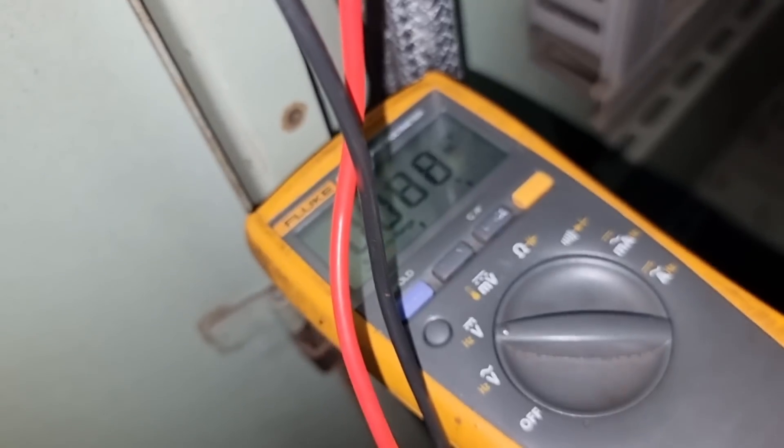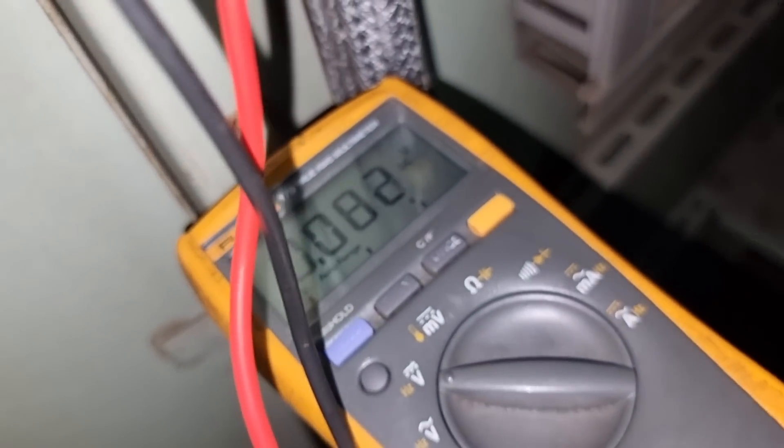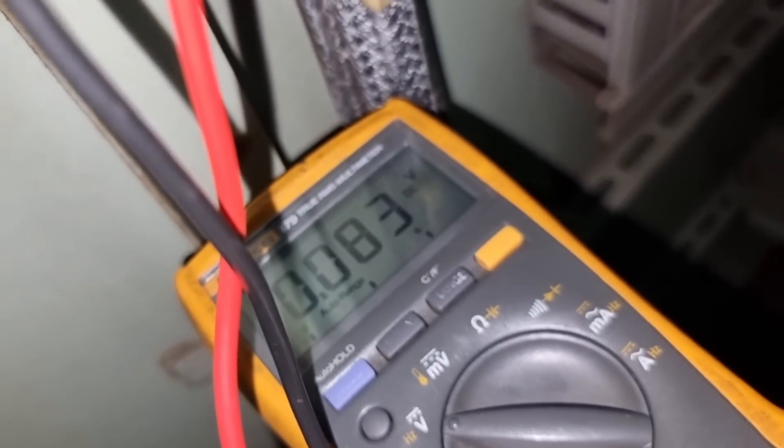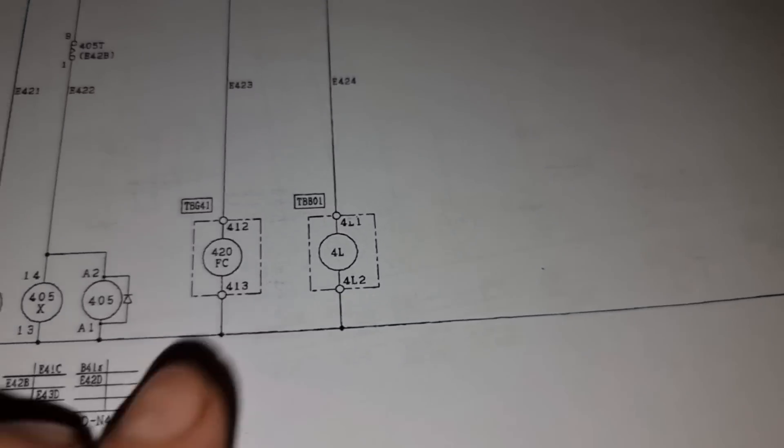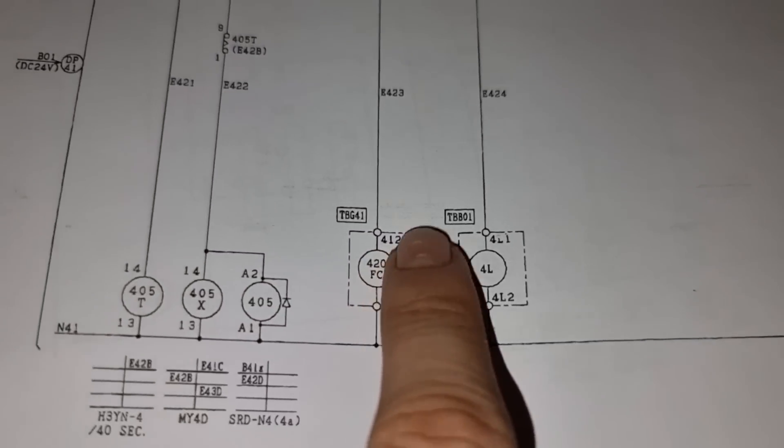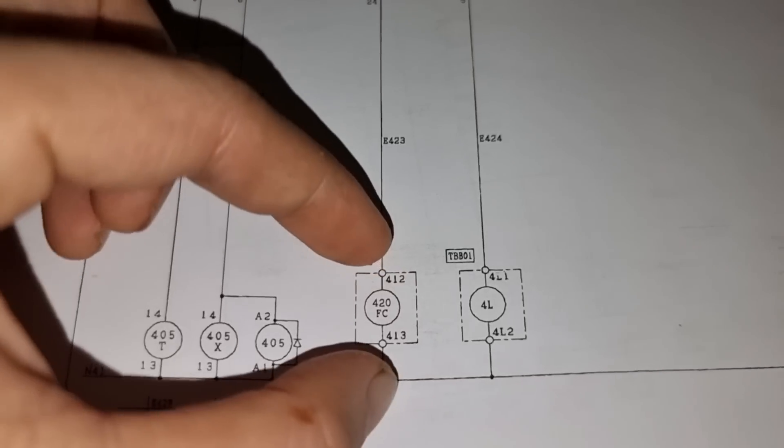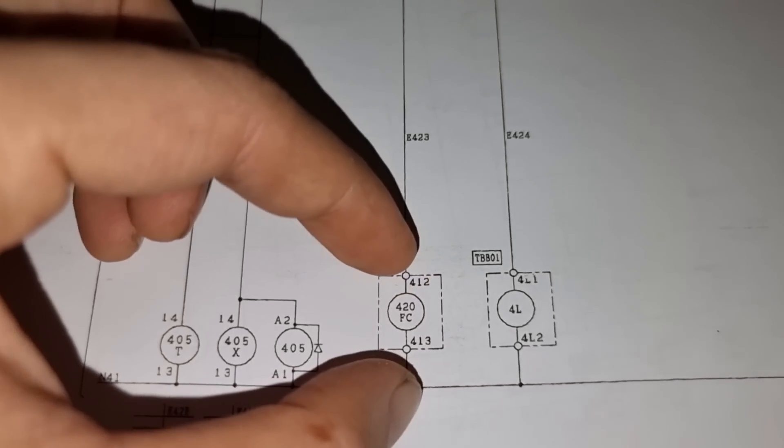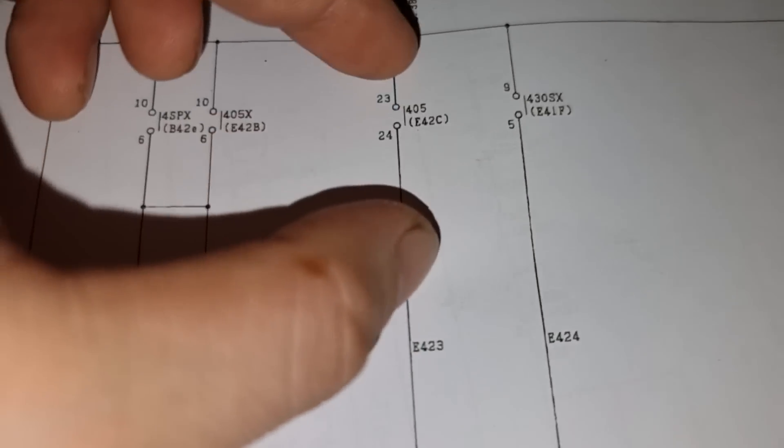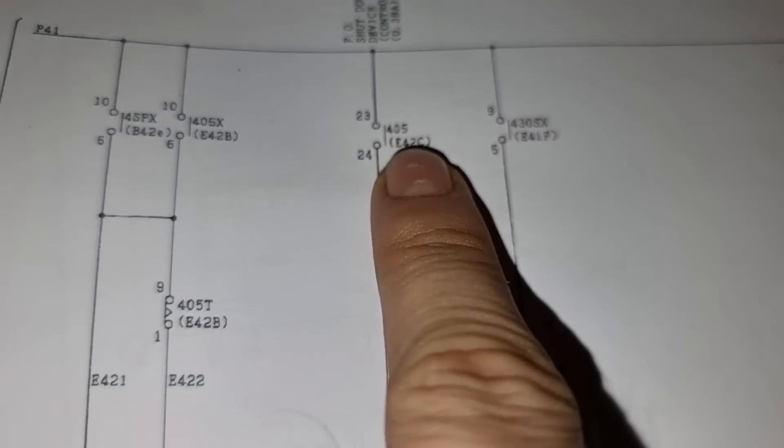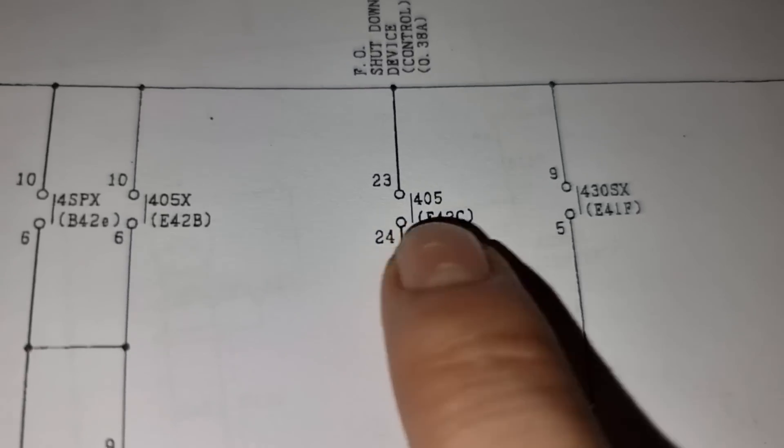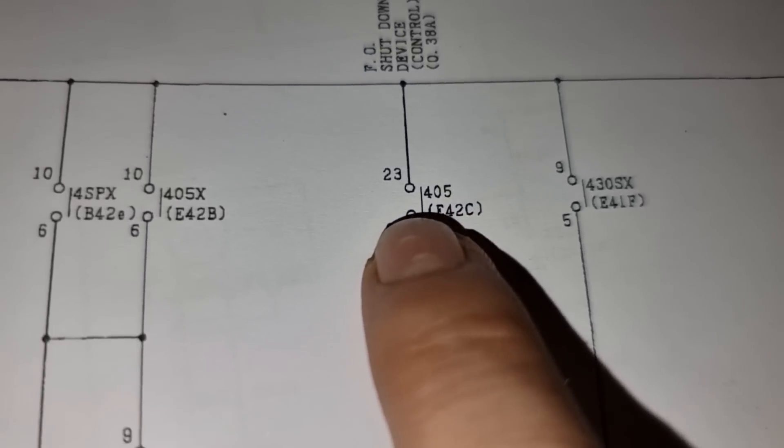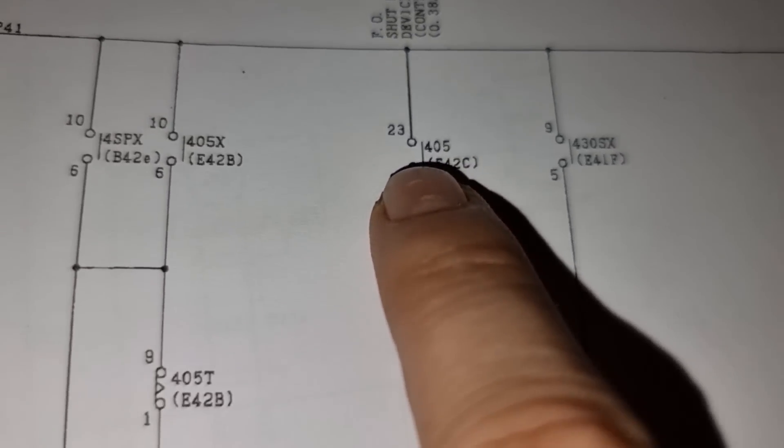But unfortunately, after doing that, we do not have 24 volts into this solenoid coil. We are not getting 24 volts onto this 412 and 413. Let's move on tracing this 405. It means that this is not closing. That is why we don't have 24 volts.